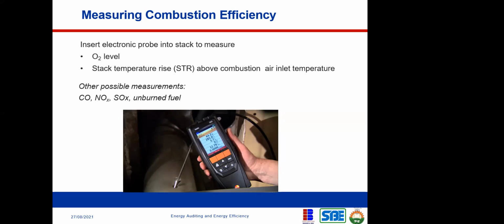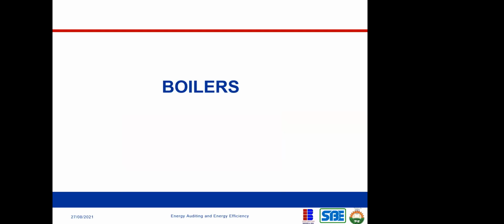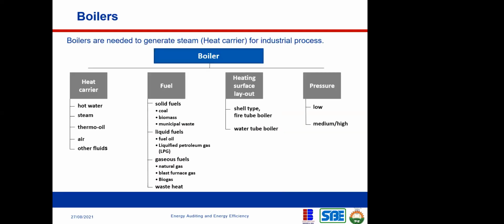But for now, just understand that for you to know if your combustion process is efficient or not, you need to insert a probe. You're looking out for elements like the carbon monoxide level, the NOx and the SOx level. All these are elements that help us to indicate if the combustion was actually complete or not. So now we're going to talk about boilers. Combustion that we talked about earlier is just a subcomponent of a boiler. We're not going to look at the boiler as a whole in totality, so we're still going to touch a little bit on that combustion sector.